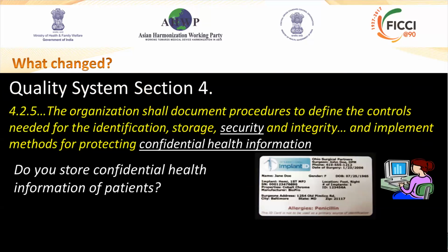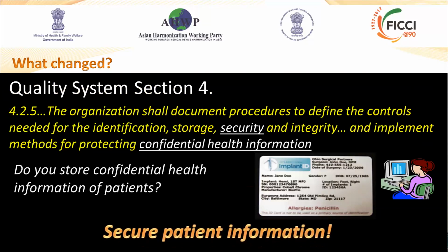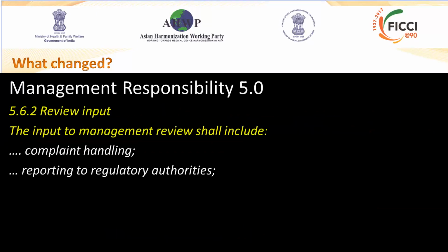There's also more requirements with regard to providing security for information that you're holding within your quality management system and keeping confidential health information confidential, especially if you have information related to patients. So if you are holding on to patient information, especially with regard to implants, which is not uncommon, that has to be especially secure within the new 13485 standard.